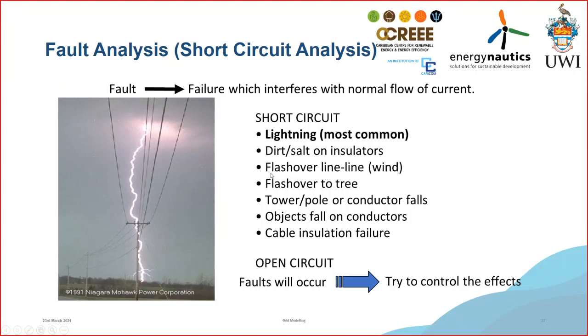Flashover, meaning that this is when wind is blowing. Maybe you get a small little storm and the line starts to swing and they touch each other, so that's when the lines are not in tension and they're actually looping too much. You can also have the trees touching these. You have a conductor fall from a pole. They say one of these just fall to ground. You could have an object fall across the conductors, or a stick fall across here. Most of the times, what happens too is that if this is going through forested area, sometimes a snake fall across there. Sometimes a bird, the wing of a bird, a hawk probably, shorts it out. Okay, or cable insulation failure, which is the one you really don't want to happen because that causes for major changes.